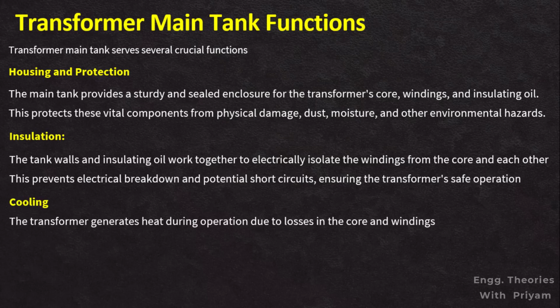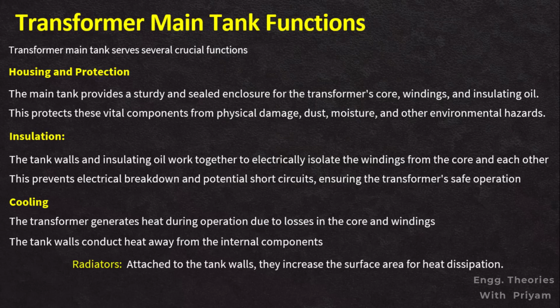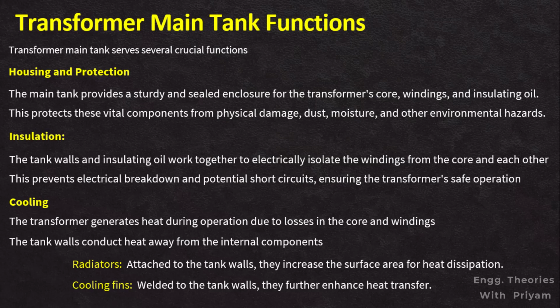Cooling. The next function the transformer tank serves is cooling. The transformer generates heat during operation due to the losses in the core and windings. The transformer's main tank plays a vital role in dissipating this heat. The tank walls conduct heat away from the internal components, and some tanks incorporate additional cooling features like radiators, which are attached to the tank walls. They increase the surface area for heat dissipation. Cooling fins are welded to the tank walls. They further enhance the heat transfer. Forced air or oil circulation systems are used in large transformers for efficient cooling.